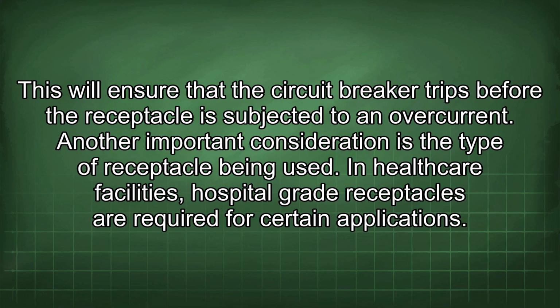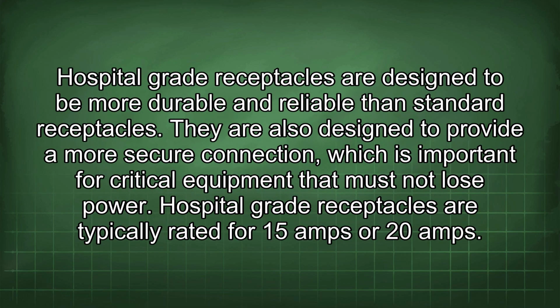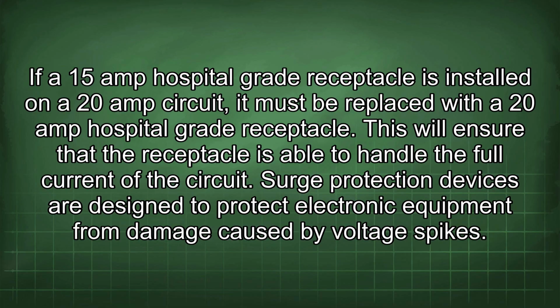Another important consideration is the type of receptacle being used. In healthcare facilities, hospital-grade receptacles are required for certain applications. Hospital-grade receptacles are designed to be more durable and reliable than standard receptacles. They are also designed to provide a more secure connection, which is important for critical equipment that must not lose power. Hospital-grade receptacles are typically rated for 15 amps or 20 amps. If a 15 amp hospital-grade receptacle is installed on a 20 amp circuit, it must be replaced with a 20 amp hospital-grade receptacle. This will ensure that the receptacle is able to handle the full current of the circuit.